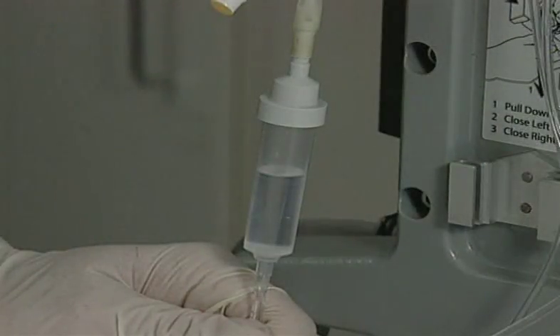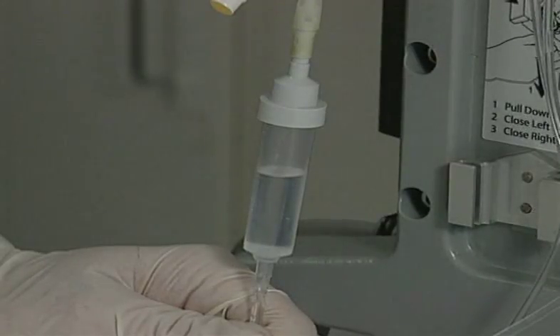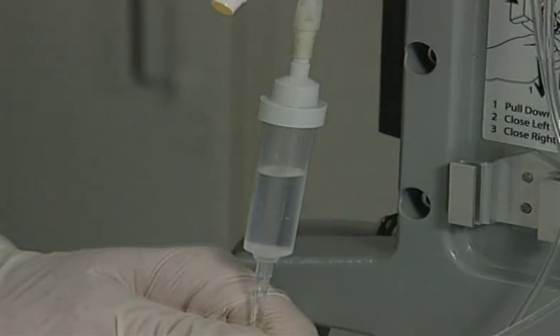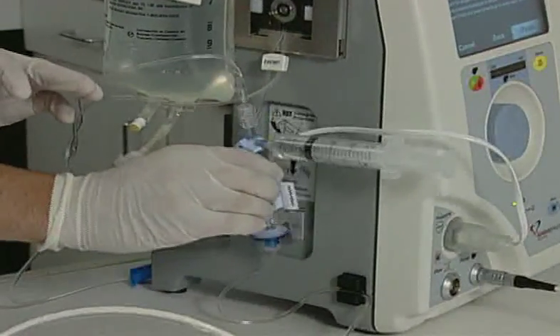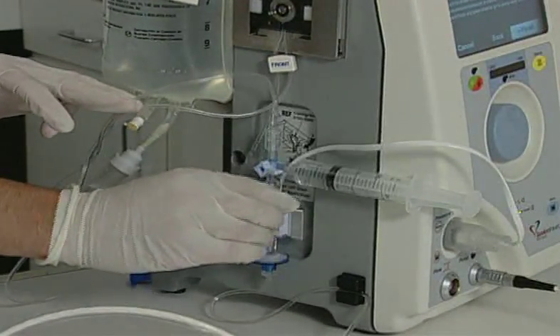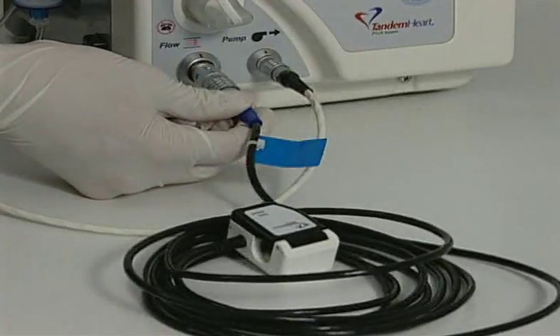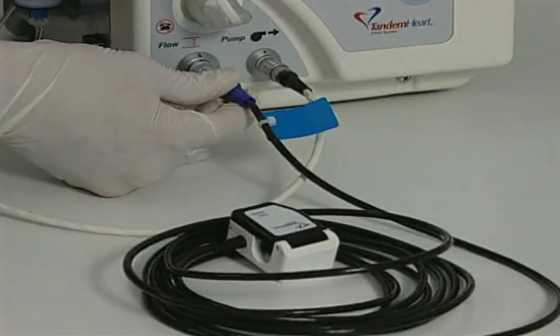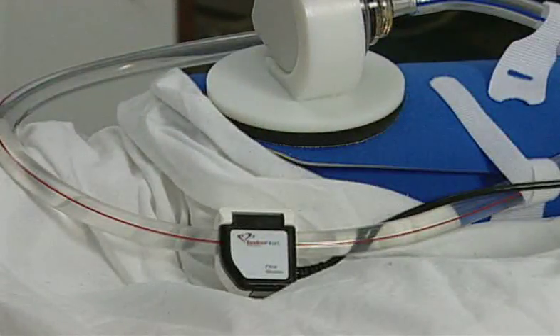Check for drips in the infusion assembly drip chamber. Controller must be powered on and roller clamp and stopcock must be open. Verify that 10 plus or minus 3 drops per minute are observed in the Infusate drip chamber. Place the pressure transducer in the mounting bracket. The optional integrated flow sensor can be plugged into the controller and placed on the pump outflow tubing.